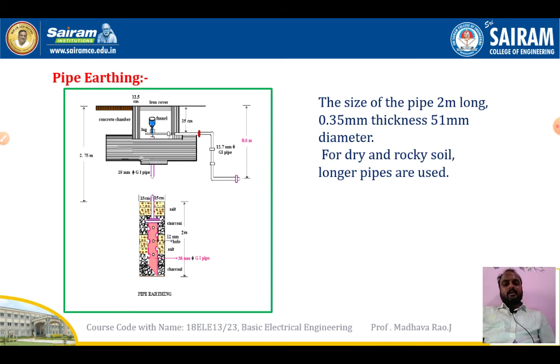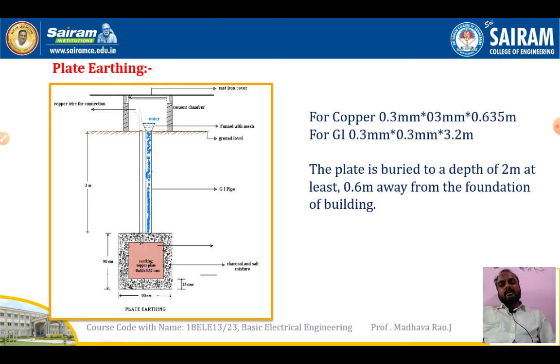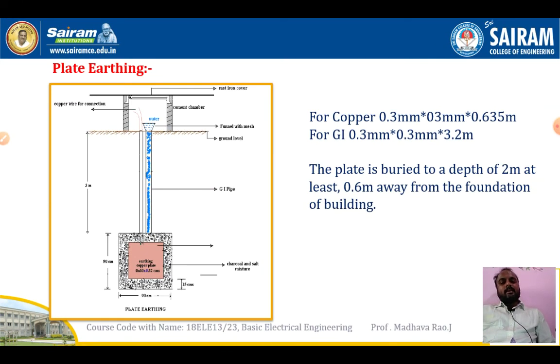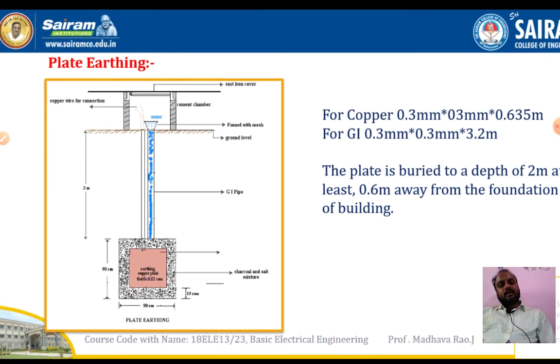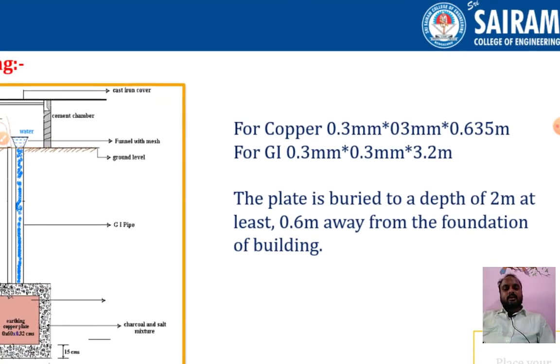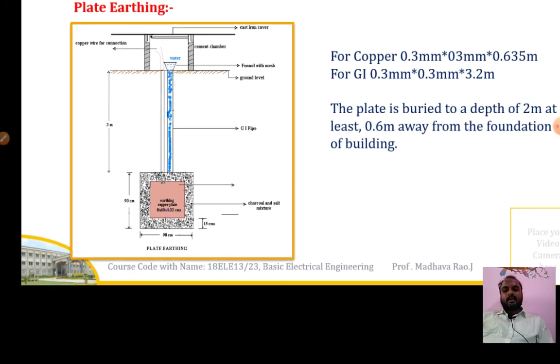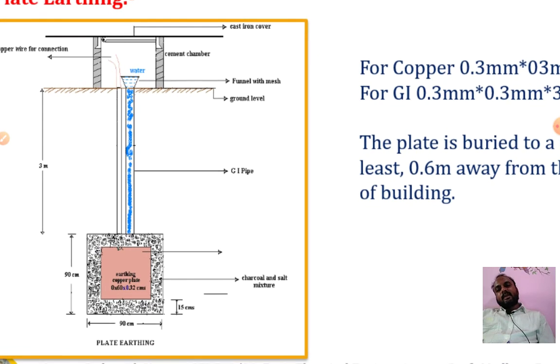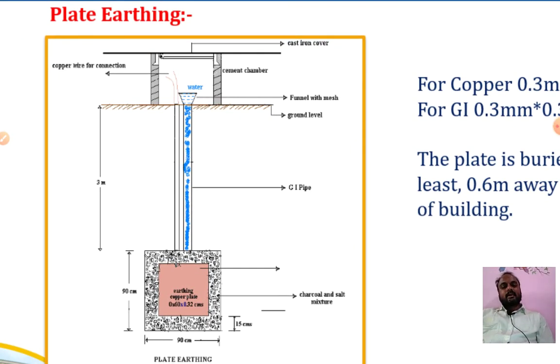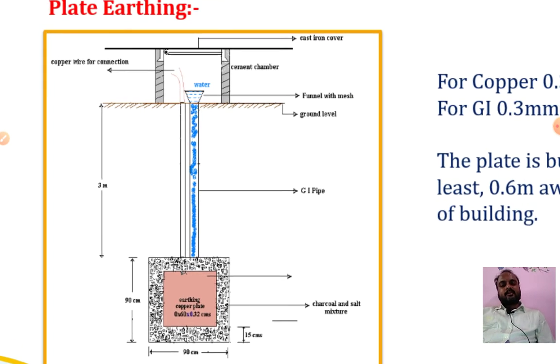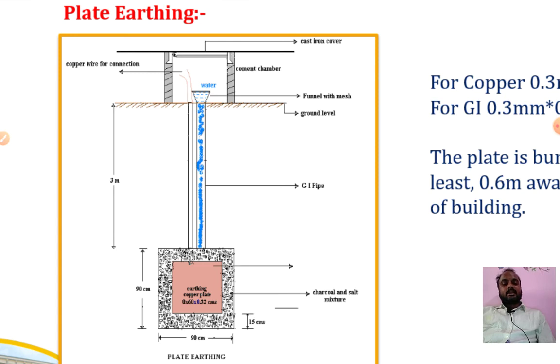Next we will see plate earthing. In this type of system, the electrode is a plate. The plate size is 0.3 into 0.3 into 0.65 for copper, and for galvanized iron 0.3 into 0.3 into 3.2. So this is the specification of the plate. The depth of the plate should be 2 meters and at least 0.6 meters away from the foundation of the building, right? Here, we call this plate earthing because the earth electrode shape is a plate.